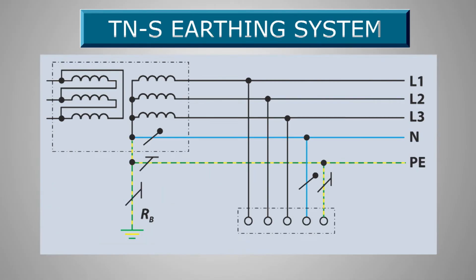TNS earthing systems: in this system, the ground conductor and neutral conductor are separate throughout the distribution system. The protective conductor is the metallic covering of the cable supplying the installation. All the exposed conductive parts of the installation are connected to this protective conductor, or via the main earthing terminal of the installation.